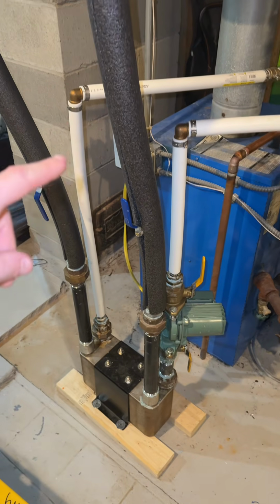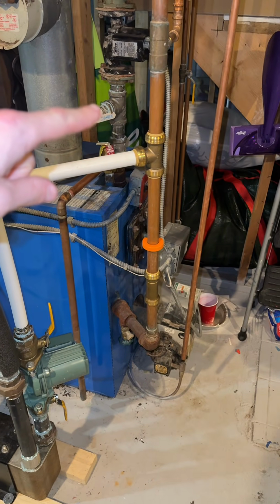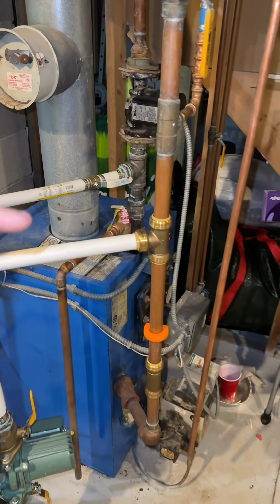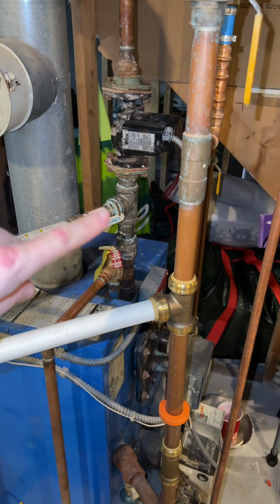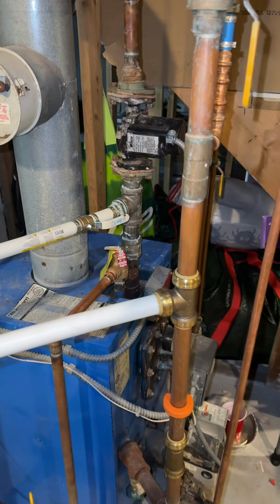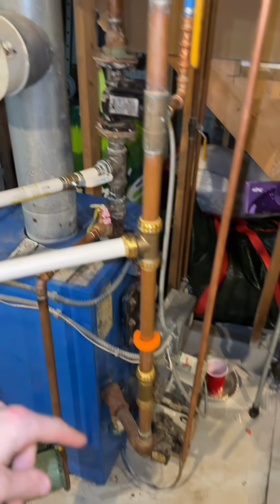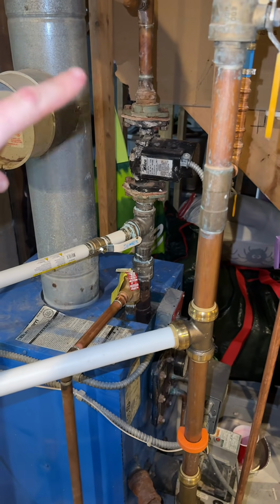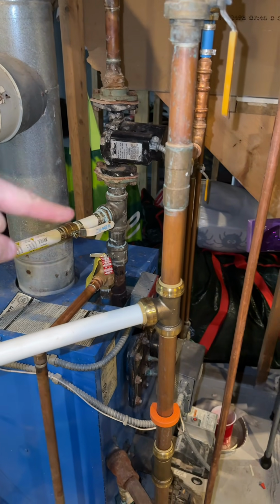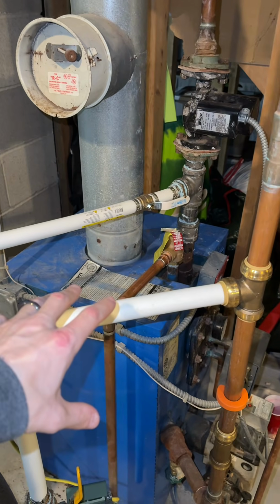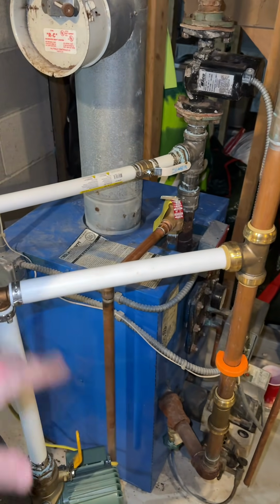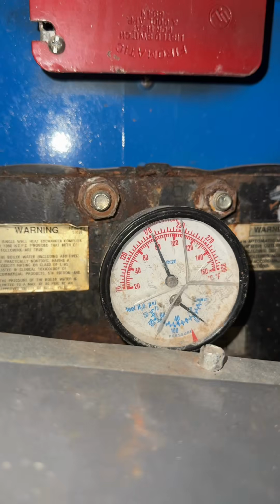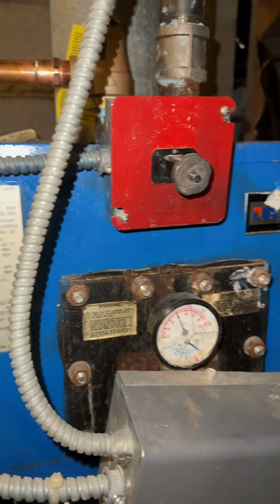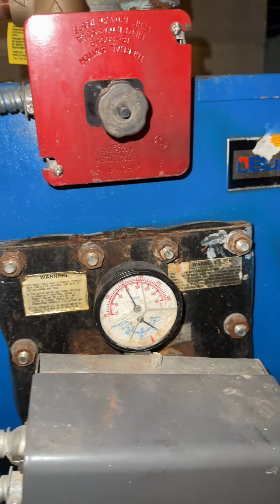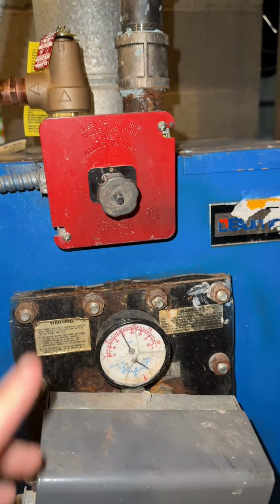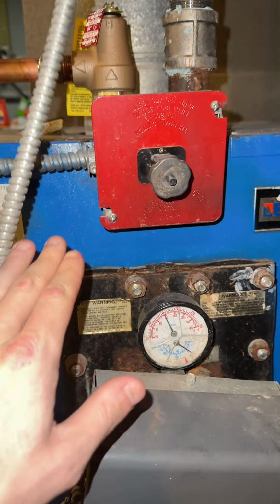So that hot water then comes up, goes over, goes into this T. If the house is calling for heat, the hot water goes up, services that, and then comes back down. But if the heating system's off, that water is just going to go down, heat this tank, and back up, and just continuing to circulate. Right now, the water temp in this boiler is at 175 degrees. Because my heat is on, everything's circulating, it's losing some heat in here.